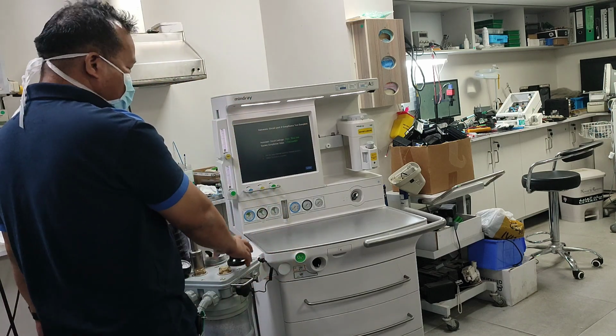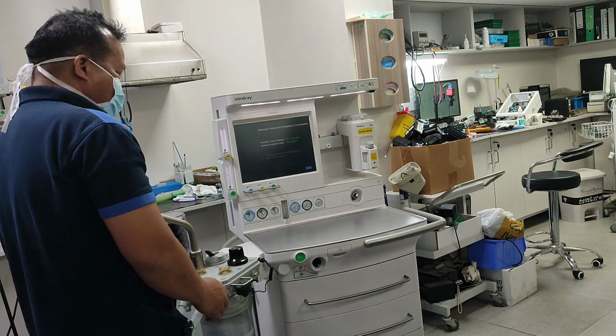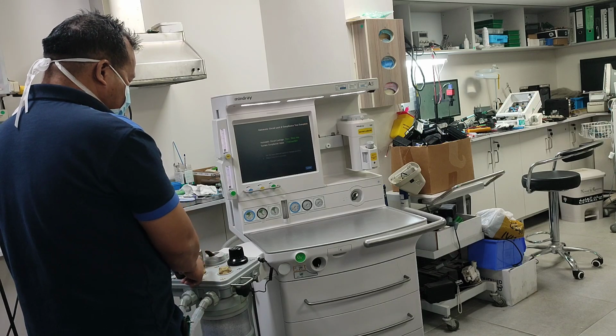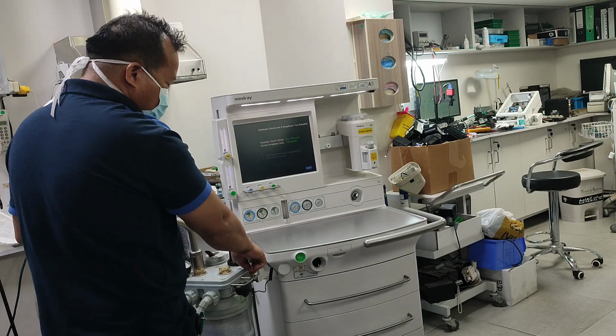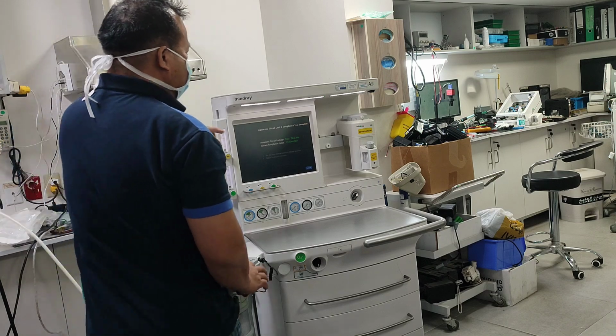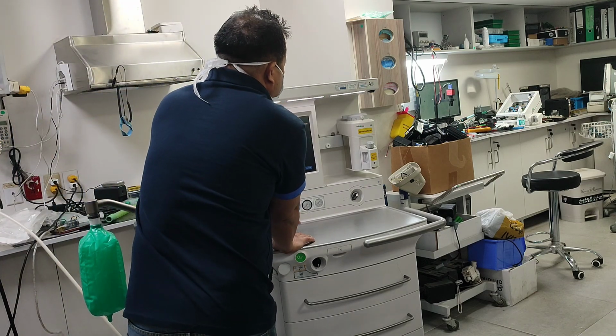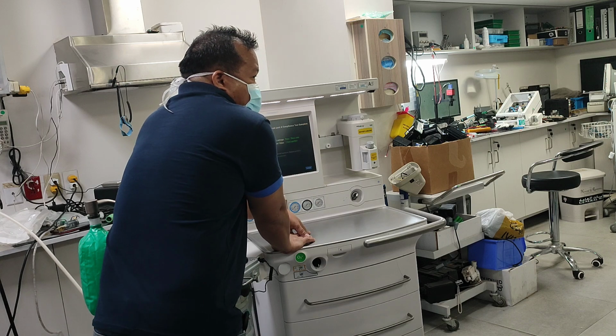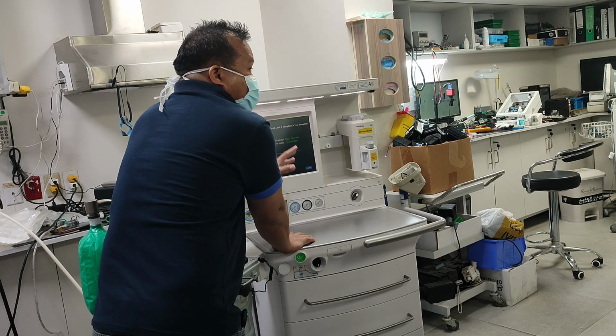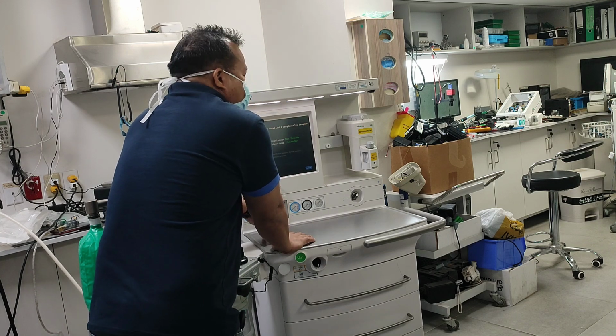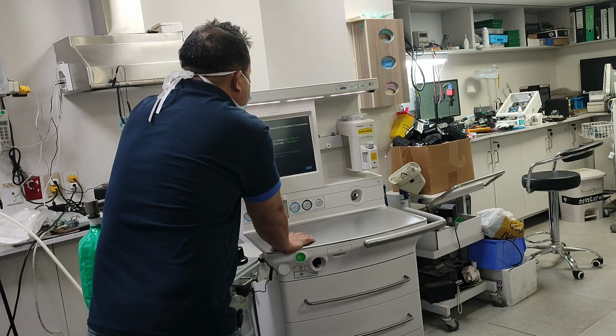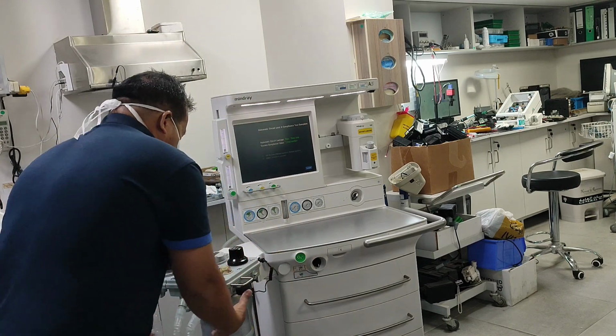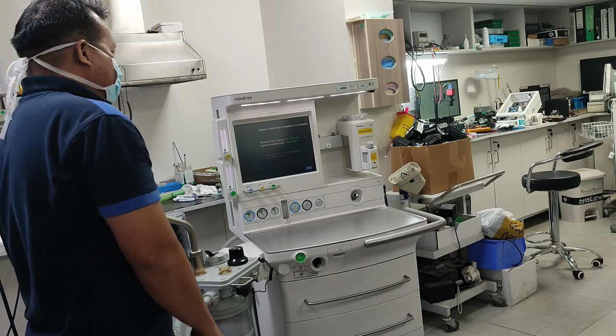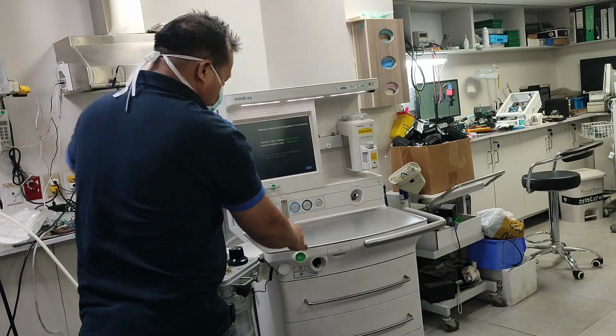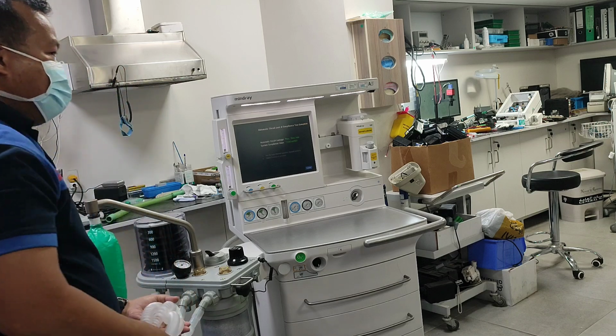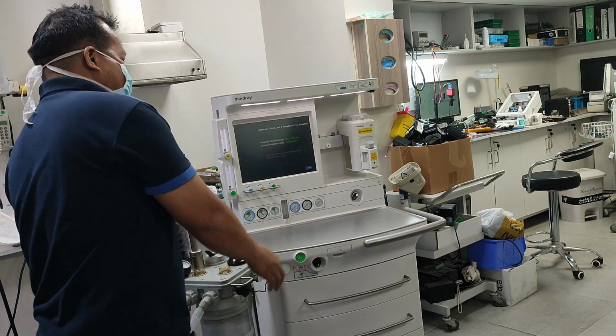Or there is a small leak in the APL or in the bag or in the screw here. We don't know where the leak is, but it's very minimal. 70 ml is acceptable. The maximum is 350 ml. The machine can compensate until 350. More than that, you should check that leakage. The automatic circuit leakage compliance, meaning this 70 ml, is the leakage from this part here.